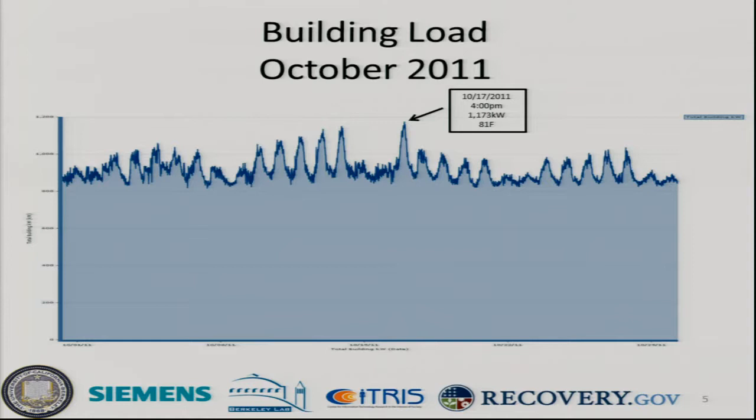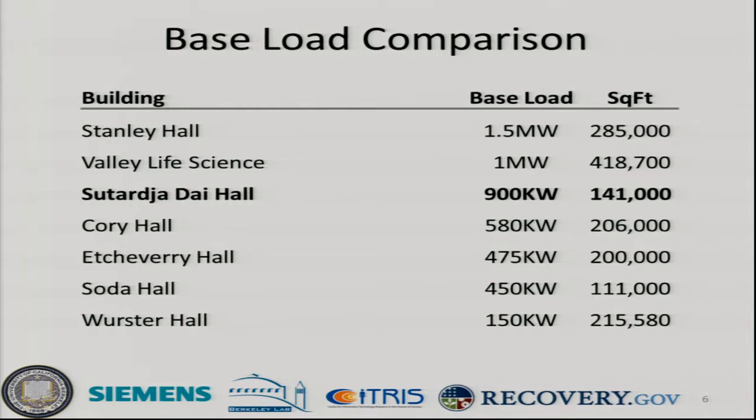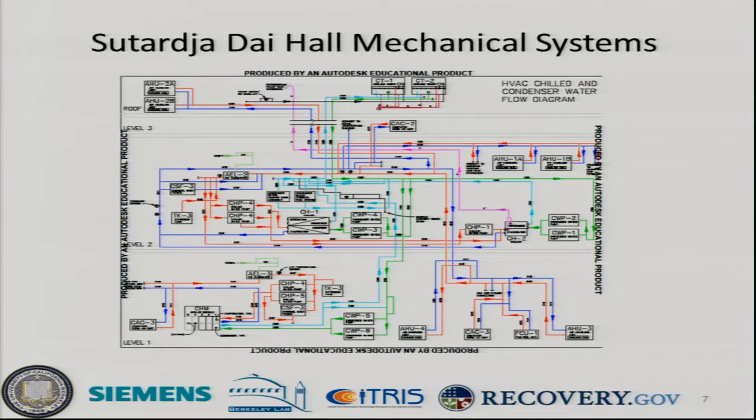This is a load profile for the month of October. We're right around a 900 kilowatt base load. On Monday the 17th at 4 p.m., we were right around 1.1 megawatts, and it was about 81 degrees that day. You can see the weekends versus Monday when it was pretty hot and there was substantial demand on the grid. Comparing to other buildings on campus: Sutardja Dai is 141,000 square feet approaching a megawatt base load; Stanley Hall is 285,000 square feet at about 1.5 megawatts; Valley Life Sciences Building is about a megawatt; and Wurster Hall is around 150 kilowatts.